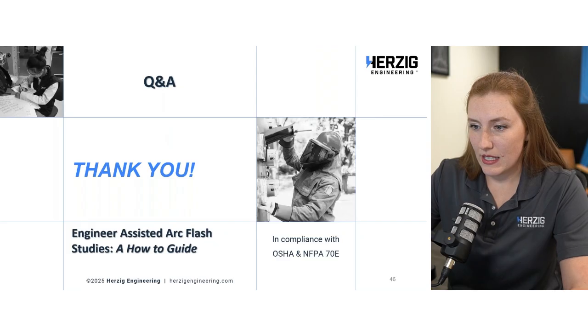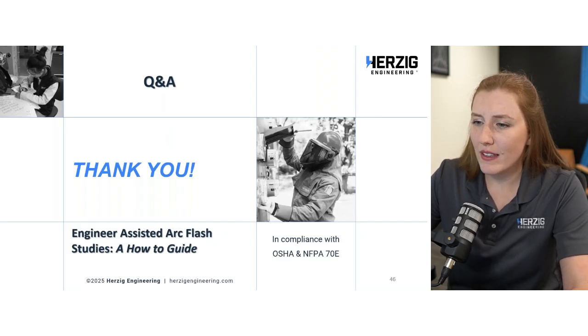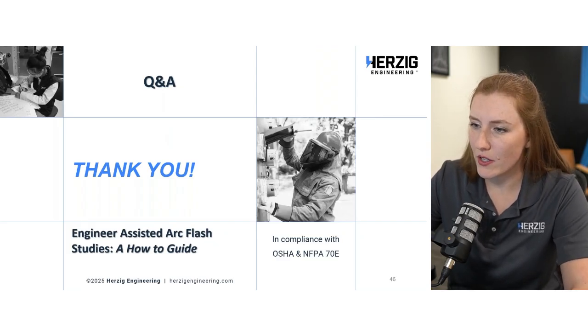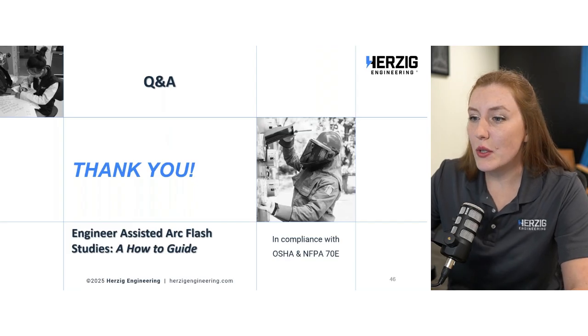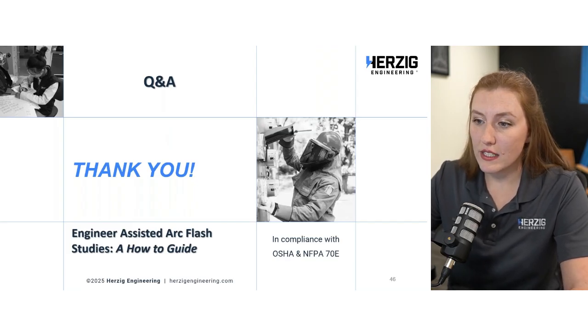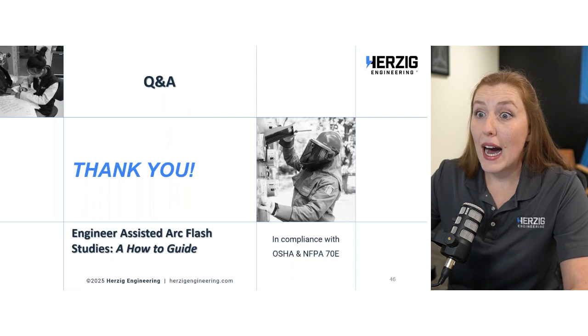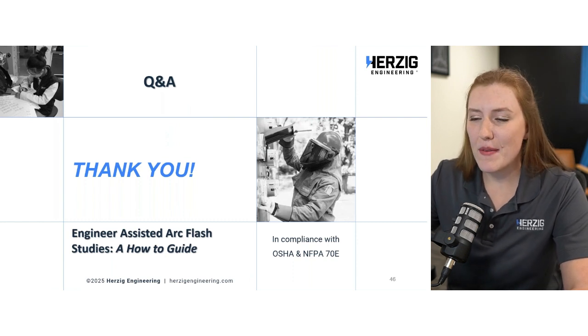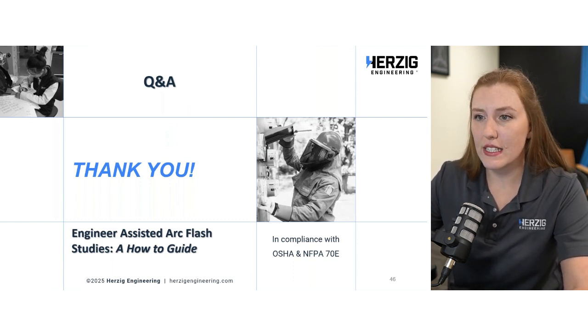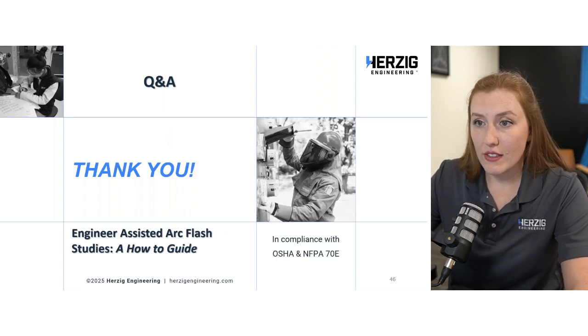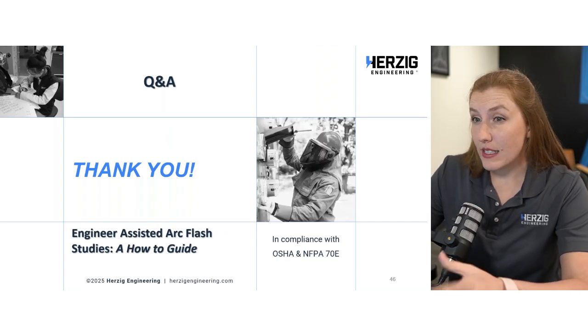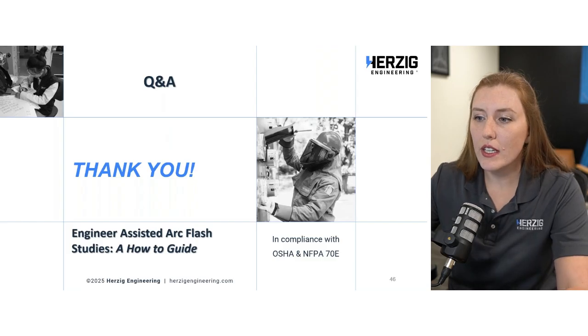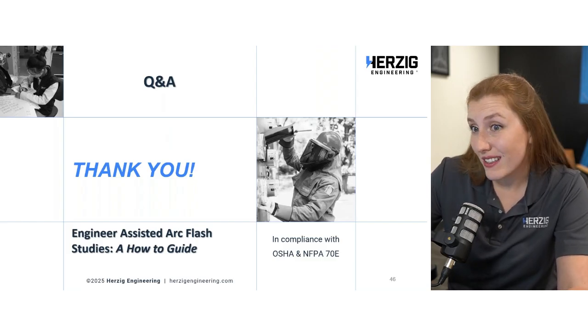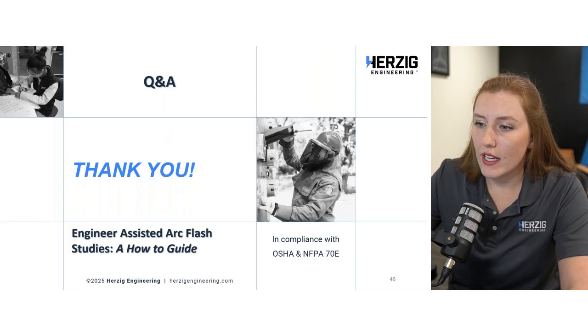Maintenance-free UPSs is an example. Okay, I could see that maybe. Talking about that question earlier: do we need to make an arc flash study for DC systems or battery banks? Possibly, yes. There are calculations for DC systems. Batteries are getting a lot of attention recently. So depending on the size and how it's configured, the answer could be yes, absolutely. Arc flash does happen in the DC world as well.